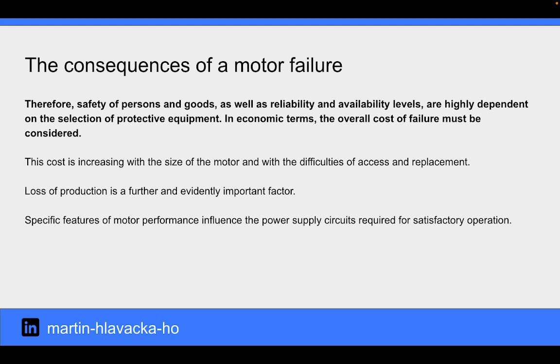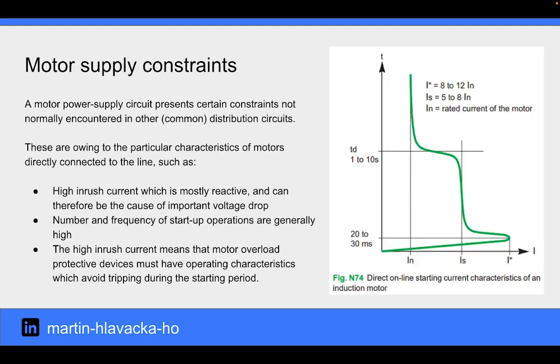Specific features of motor performance influence the power supply circuits required for satisfactory operation. Motor power supply circuits present certain constraints not normally encountered in other common distribution circuits, such as a high startup current that is mostly reactive and can therefore be the cause of important voltage drop. The number and frequency of startup operations are generally high, and the high startup current means that motor overload protective devices must have operating characteristics that avoid tripping during the starting period.